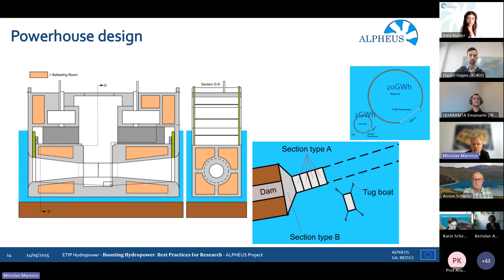This means on one side we have a dam structure, then a transition section where we come from the dam into the powerhouse section, and then the system of the caissons with the powerhouse, which are transported to the side and sunk at the right place. Of course, there is an additional problem with the seepage under the dam, which has to be controlled, because the length of the powerhouse module is shorter than the length of the dam section. And also safety, especially in the large section, we need safety between the system of blocks. We must have tightened systems, so that if some tightening problem happens between caissons, it will be easily located in the system.